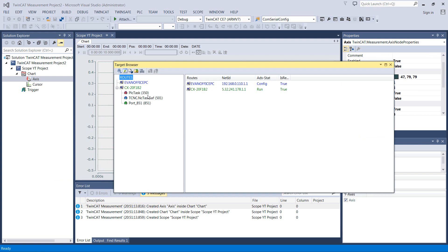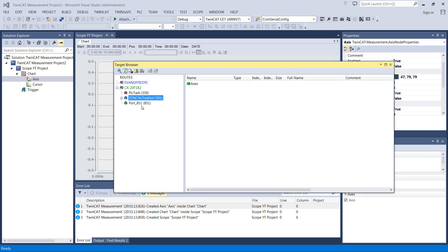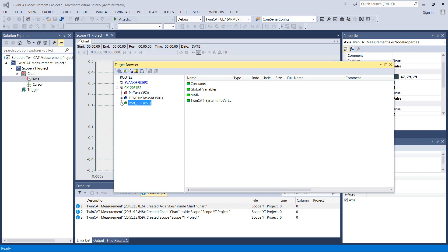So in here we've got our PLC task, our NC task which would be what's running the axes and then port 851. Back on TwinCat 2 every runtime used to run on 801, 802, 803, 804 because you are allowed up to four PLC runtimes concurrently with TwinCat and I believe that's a per core thing.